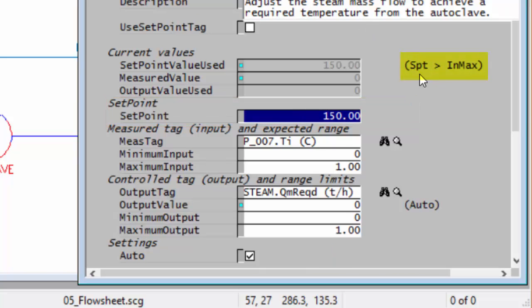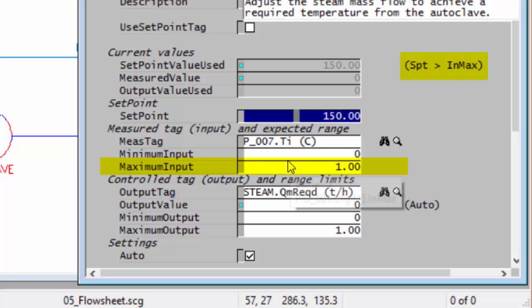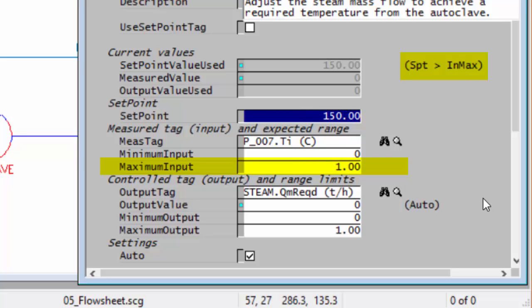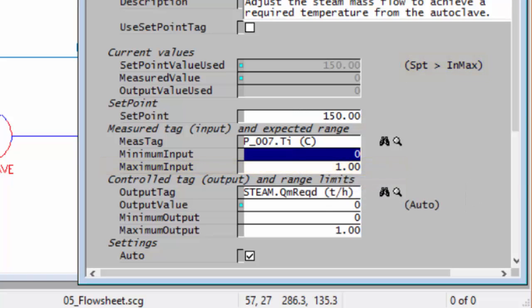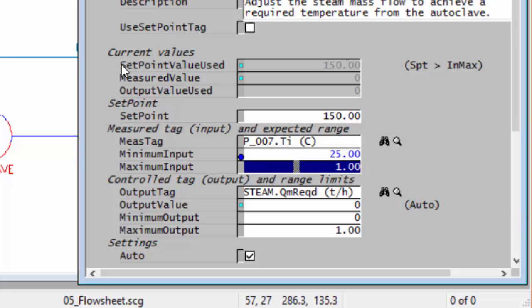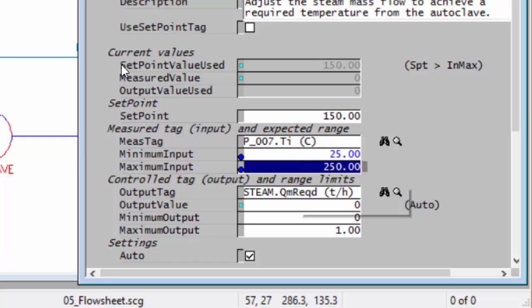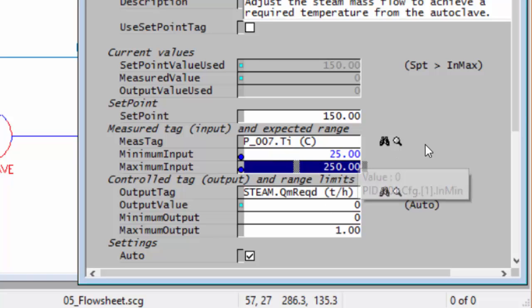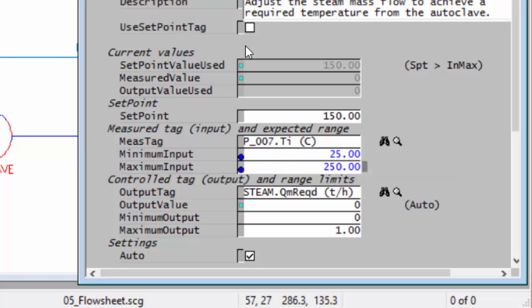If I click on the OK button you'll see now I get this warning that my set point is actually greater than my InMax. The InMax is the greatest temperature that it would expect to see. You can see at the moment the minimum input is zero and the maximum is one. So let's change that. We'll say we don't expect it to get less than ambient temperature 25 and the maximum 250 because we're using steam at 275. So 250 seems a reasonable value. If I click on the OK button now you'll see that that warning has gone away.